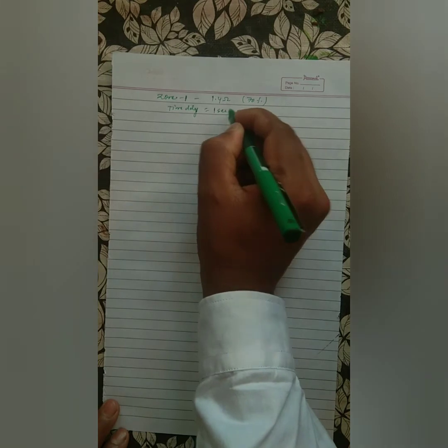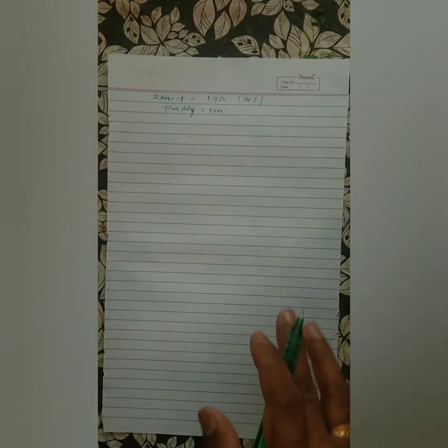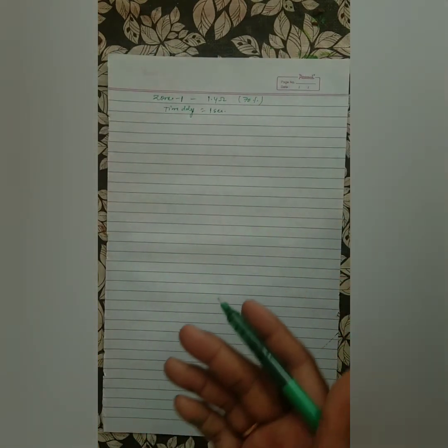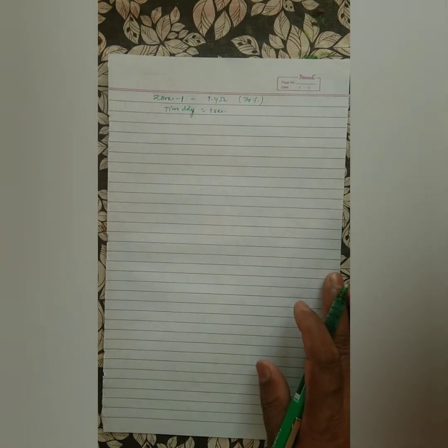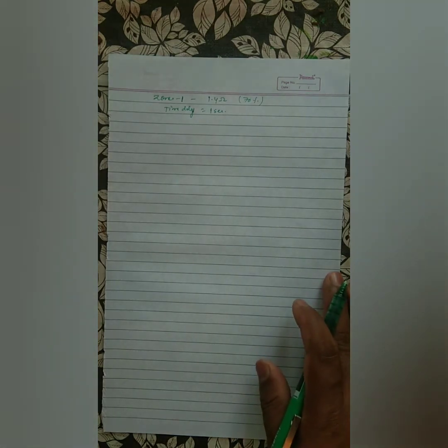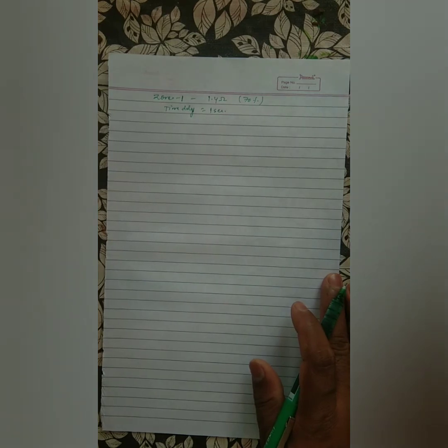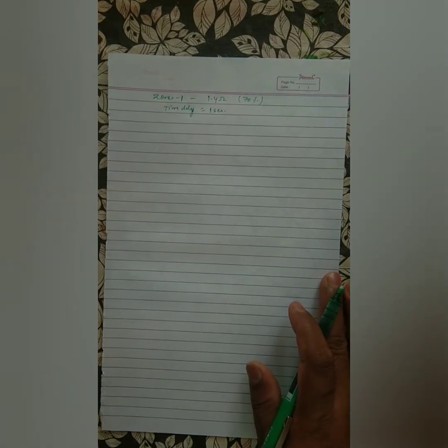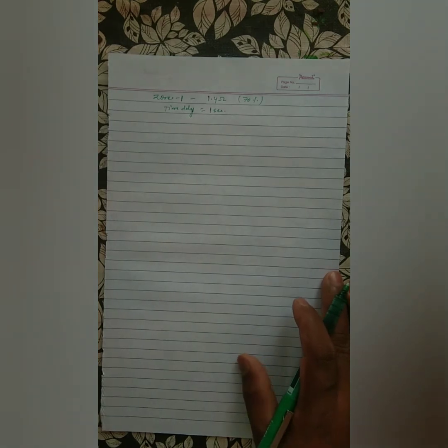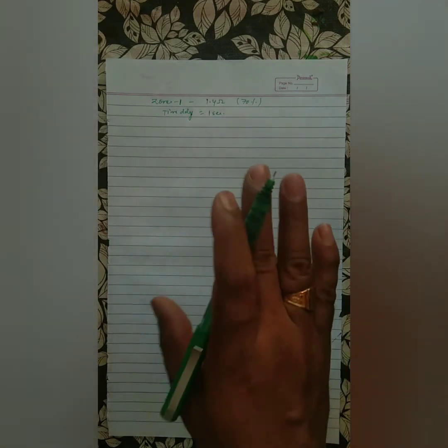In line protections, we actually divide the zone into 4 parts: zone 1, zone 2, zone 3 and zone 4. Zone 1 is taken as 80% of the line length, and which is instantaneous. That means there is zero time delay for that. If anything happens in the zone, then it trips the circuit instantaneously. So here in the generator's protection settings, we have time delay of 1 second in zone 1.